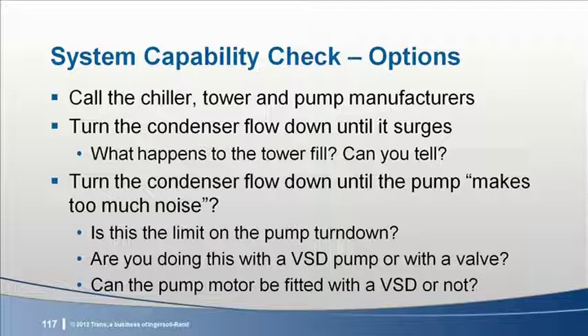What if the chiller was originally selected for 2 GPM per ton, but for whatever reason the operator gave it 3 GPM per ton? If you turn down the condenser flow, you might not ever get that chiller to complain. Maybe it's the pump that starts to make noise first, or the net positive suction head starts to get too low. If the condenser pump doesn't already have a variable speed drive, is the pump motor rated for it?